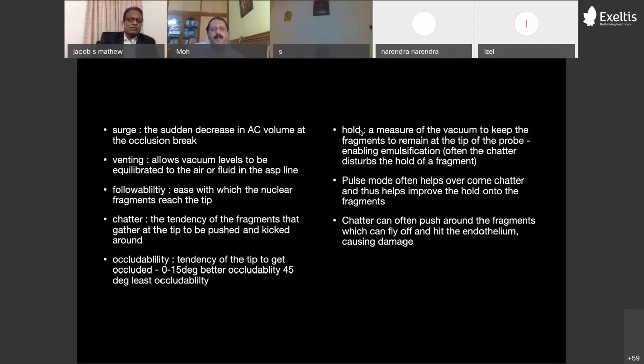Chatter: because the tip is moving at such a fast agitation speed, like 30,000, 40,000 hertz in a second, the fragments tend to get pushed around or kicked around, and this chatter causes the fragments to get thrown off from the tip. So the hold is affected because of the chatter as well. Actually, the pulse and the breaks in between help the followability to be better and the hold to become better. So that is the reason why you go for a pulse mode or hyper pulse and things like that, so that you can reduce the chatter and improve your followability and also the hold.